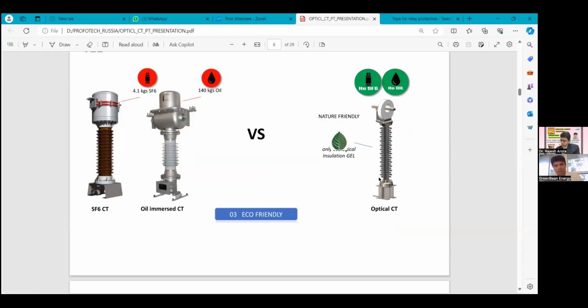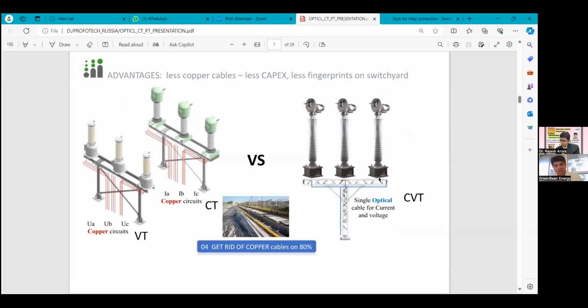Here they have one solution which is a combined solution of optical CT and PT. In a substation, voltage transformer and current transformer are separately installed, but in the case of this CVT, no separate installation is required. There is a combined unit that is called CVT. We can measure both current and voltage in a combined module. So you can remove the copper cables and their laying and other things, and you will need only one single fiber optic cable to measure the current and voltage. So cost economy wise, you will get more advantage because there are no cables. You can also save space because a single module is available which can measure both current and voltage.